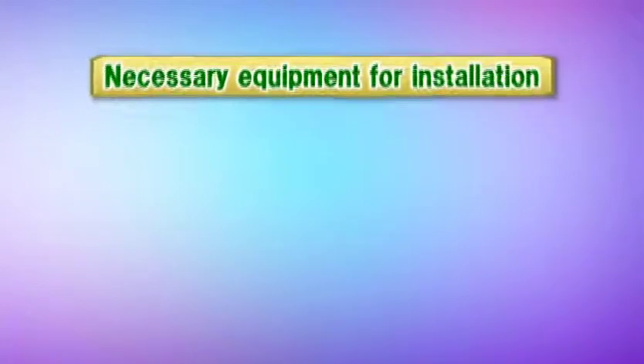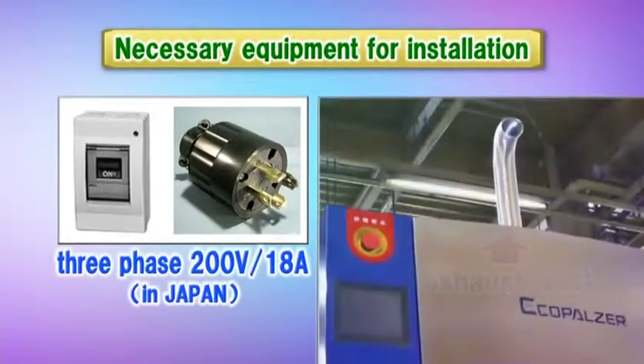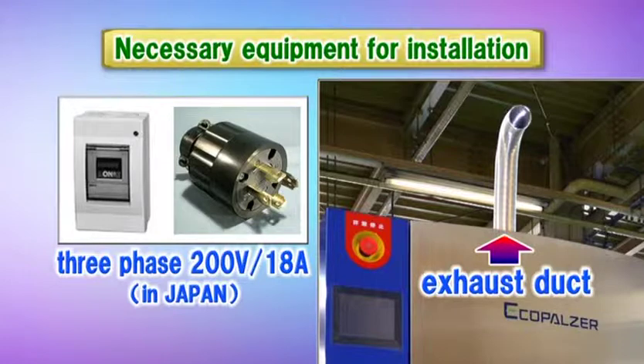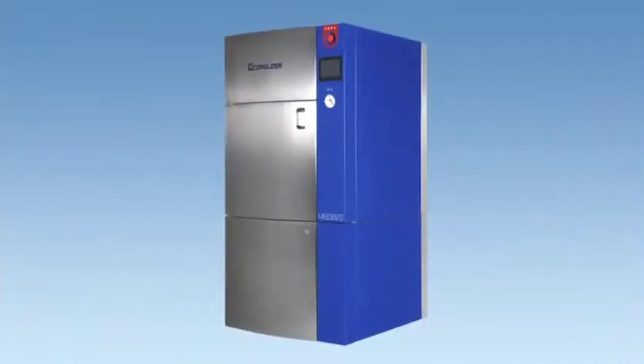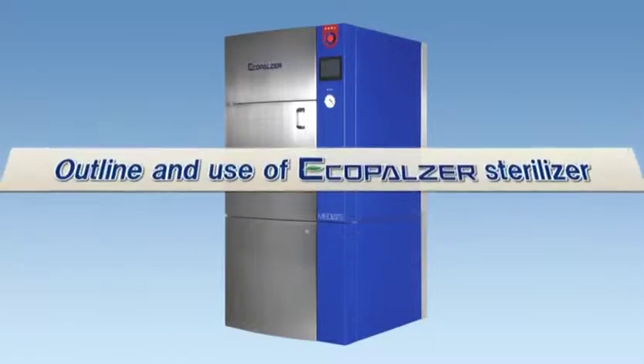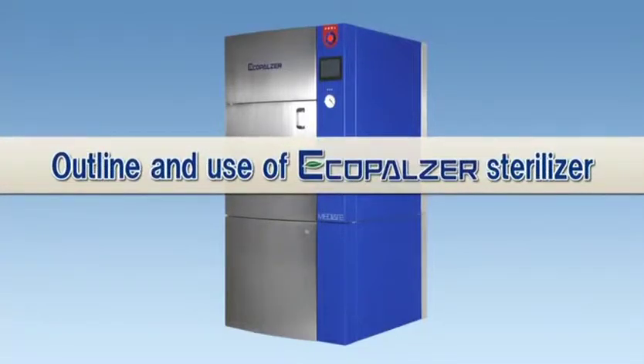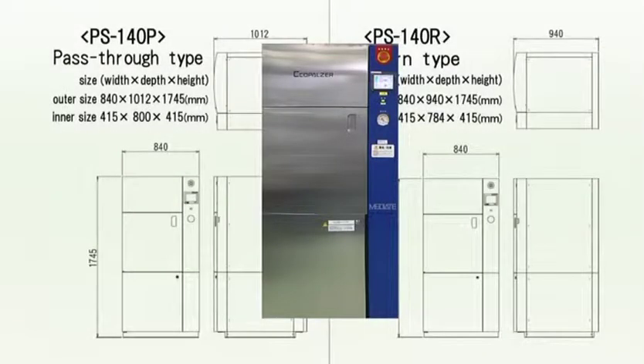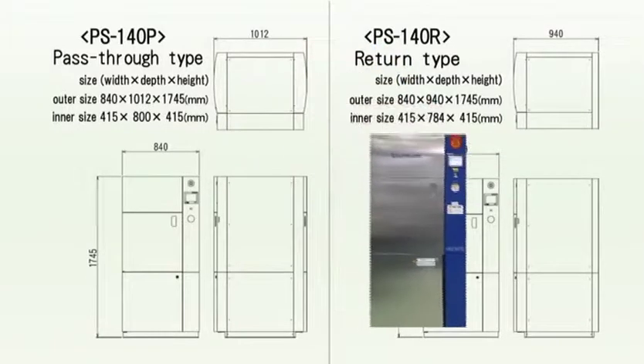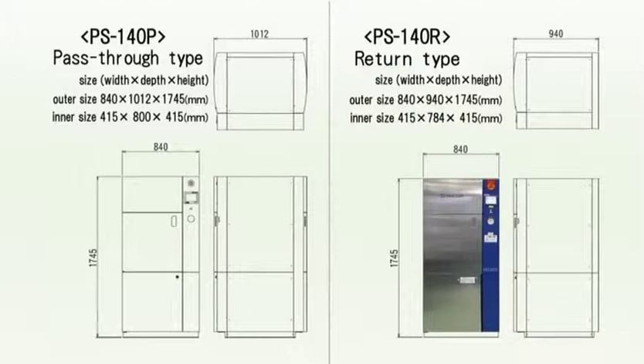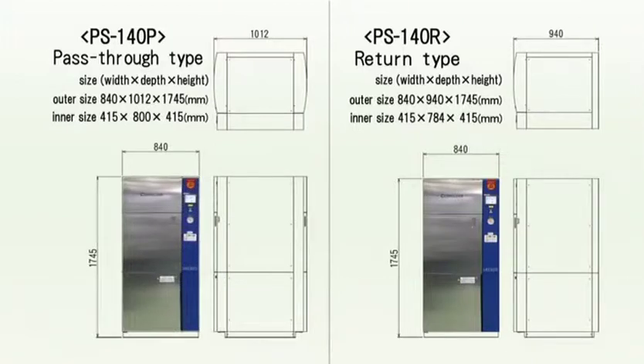To install the ECOPALZER, you only need 3-phase 200-volt power supply and an exhaust duct. There is no need for water supply, drainage system, or steam equipment. We have two types of ECOPALZER. Return type PS140R has the sterilization chamber door attached only on the front side. Pass-through type PS140P has chamber doors on both the front and the rear sides.